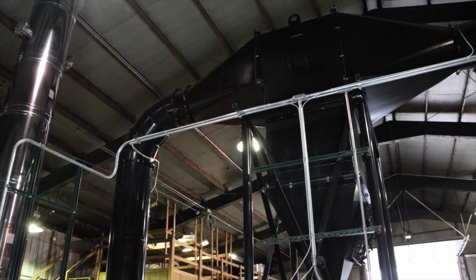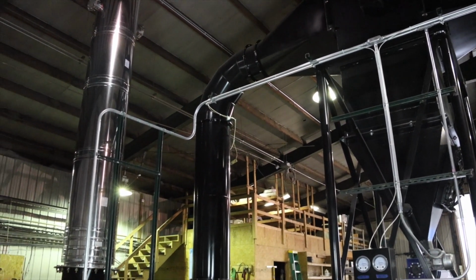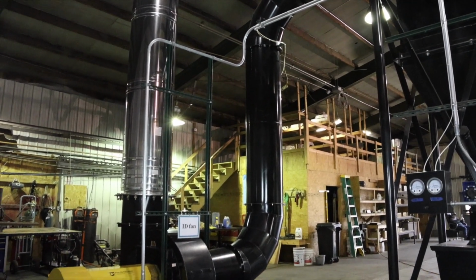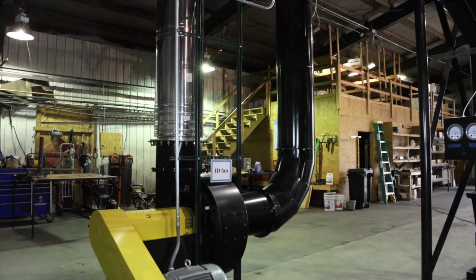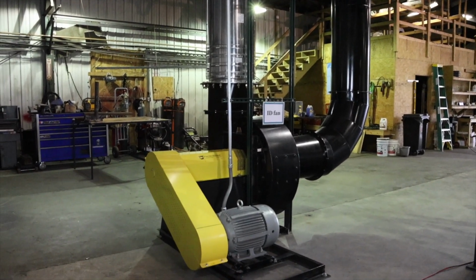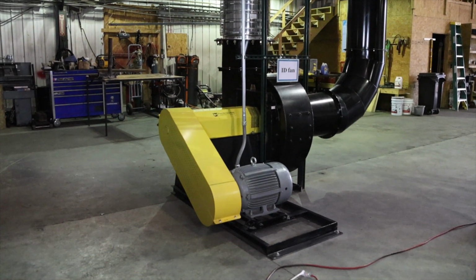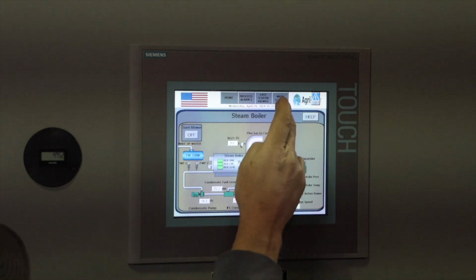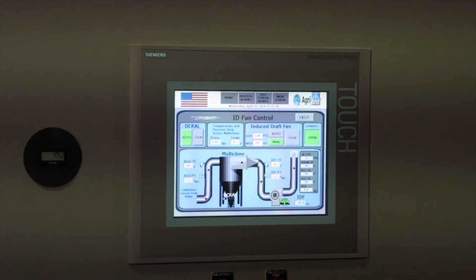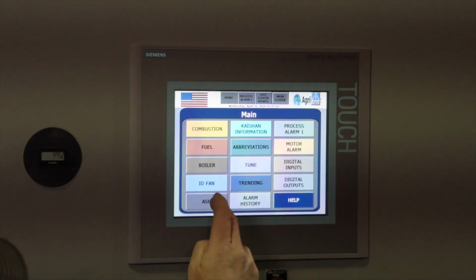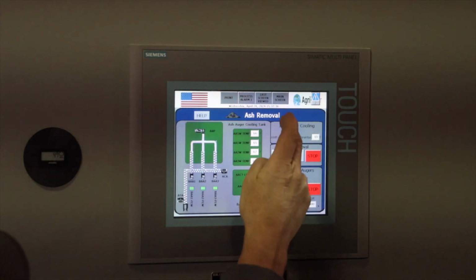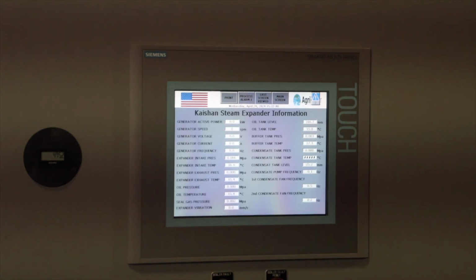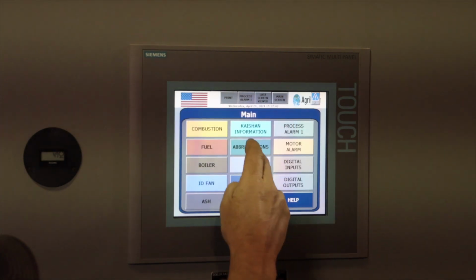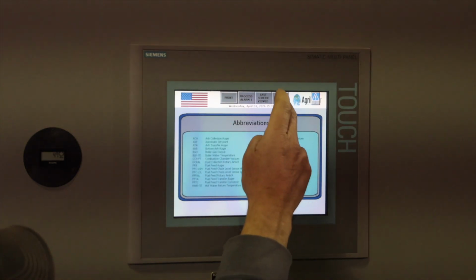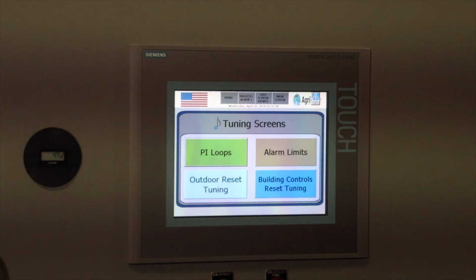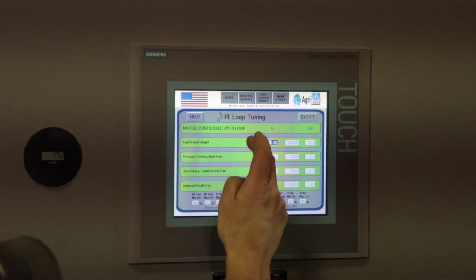The gases move to the induced draft fan, which is a fan used to maintain a constant negative pressure throughout the combustion gas stream. This fan, which operates automatically by way of a variable frequency drive, ramps up or down to make more or less steam based on load demand. The combustion system and related equipment are monitored and controlled by way of a colored HMI touchscreen. All information, including temperatures, alarms, motor status, and operating parameters, are displayed on easy-to-read and operate animated screens specific to each part of the system. The control panel is capable of remote monitoring and operation and can be integrated into most other forms of software.